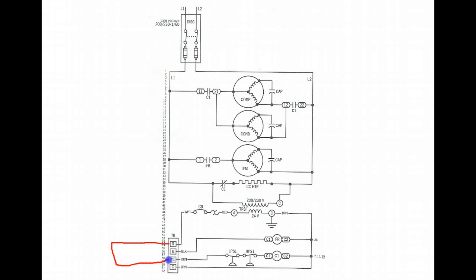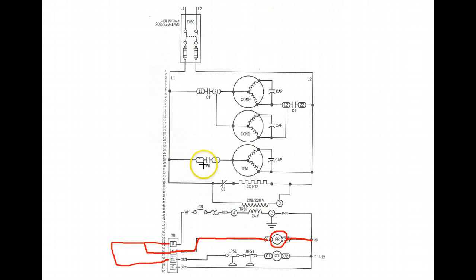That takes care of the 24 volts on the Y terminal. Then we have 24 volts on the G terminal. 24 volts comes through to the indoor fan relay — the solenoid part of the relay that energizes and closes the contacts. We find the IFR contacts up in the high voltage section. Here is the normally open indoor fan relay contact. When power is applied to the relay, that normally open contact closes, applying power to the indoor fan motor so it runs.